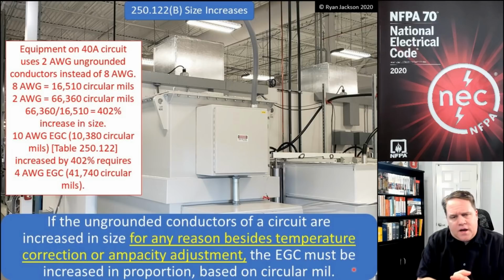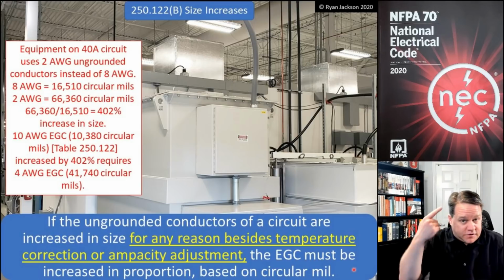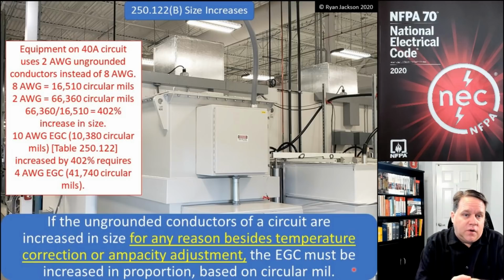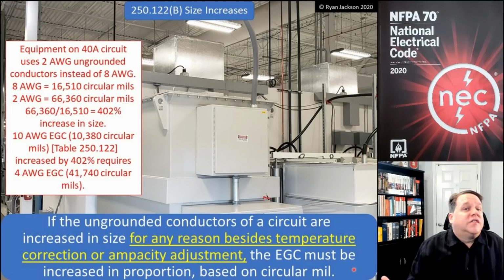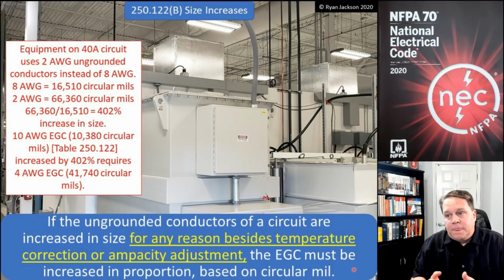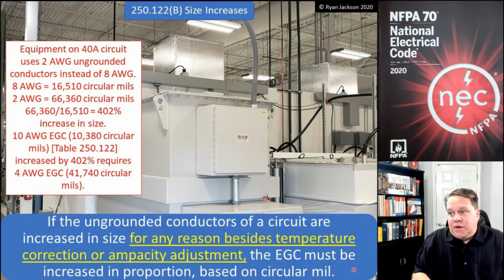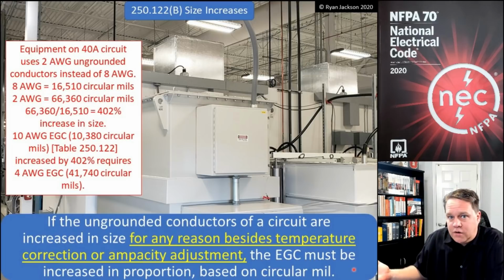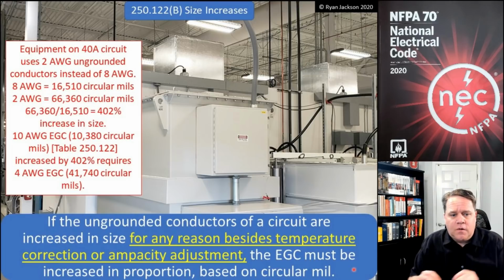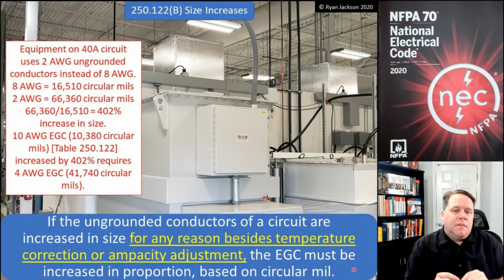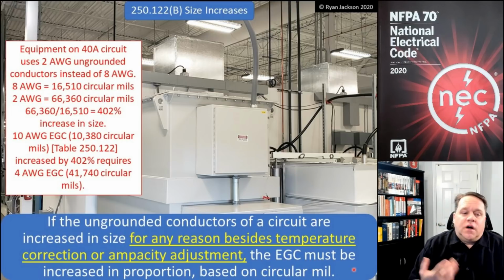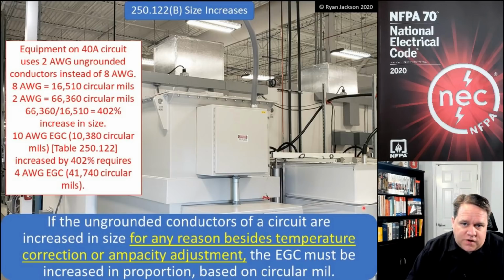If I had a 20 amp circuit, and I have, off the top of my head, 10 current carrying conductors inside of that conduit, I'm not going to be able to use 12 gauge, right? I'm going to have to apply an ampacity adjustment and might require 10 gauge conductors. So is that an increase in size? Well, no, it's not an increase because it's the minimum required to carry the load, right? So it's an increase in size mainly for voltage drop, but truthfully, any reason other than temperature correction or ampacity adjustment.